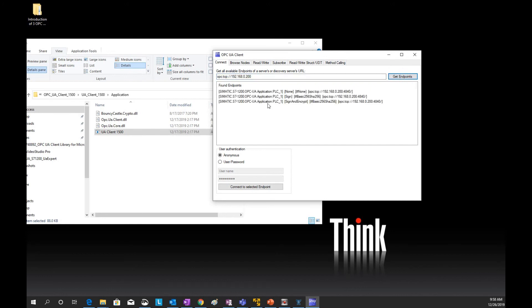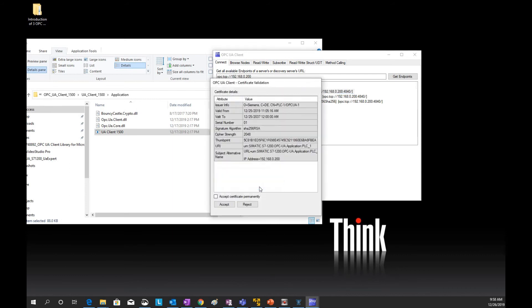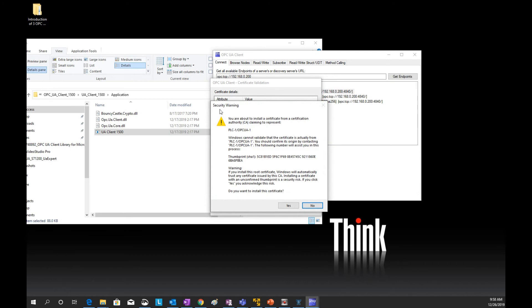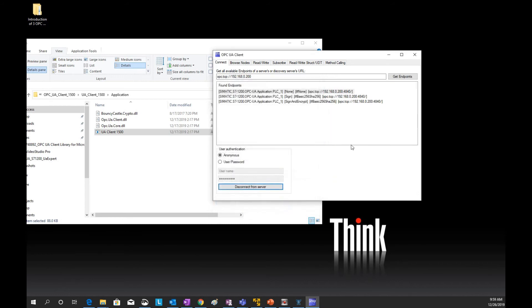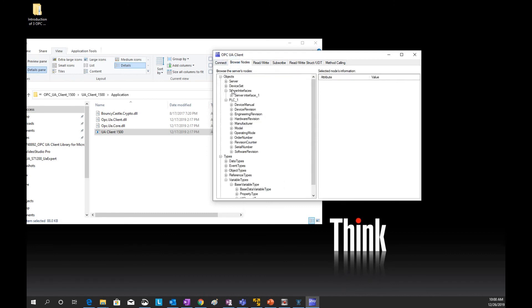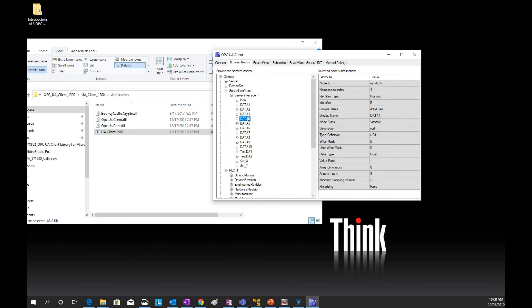Search for the server and click 'Get Endpoints'. The client has found the server. Same as before, click the non-security option and click Connect. Click 'Accept Certificate Permanently'. A security warning pops up — install the security certificate. Once the button shows 'Disconnect from Server', that means we are already communicating with the OPC UA server. Next, shift to the second tab — Browse Nodes. From here we can find, under server interface, 'server interface underscore 1', and browse through every tag.